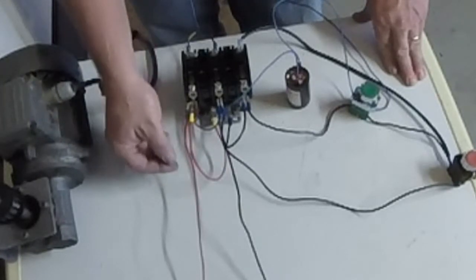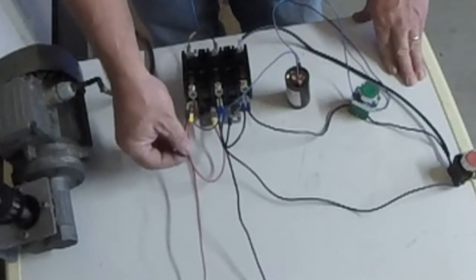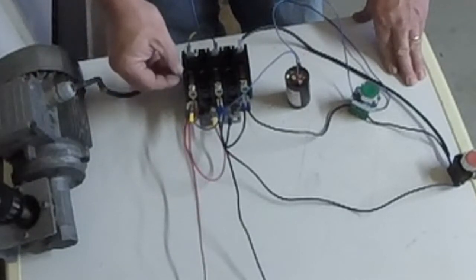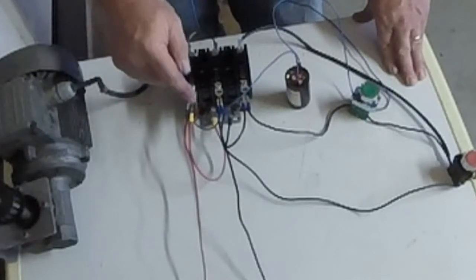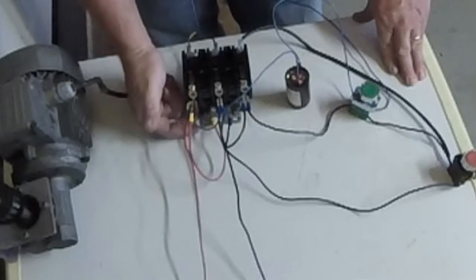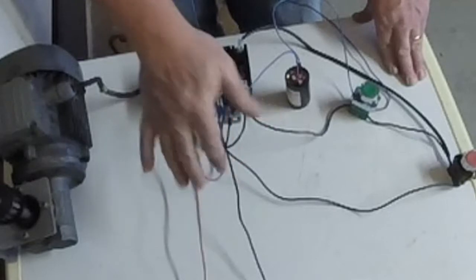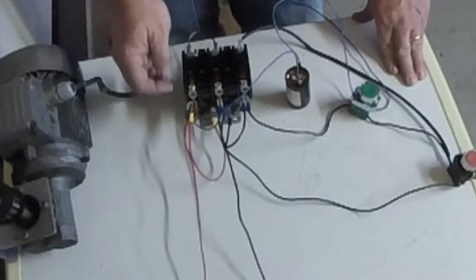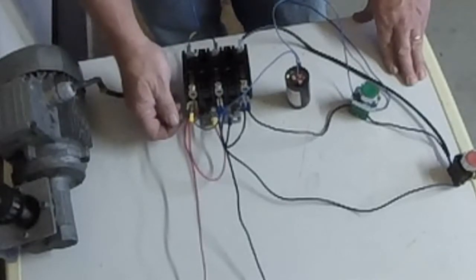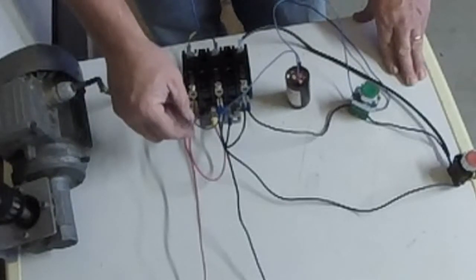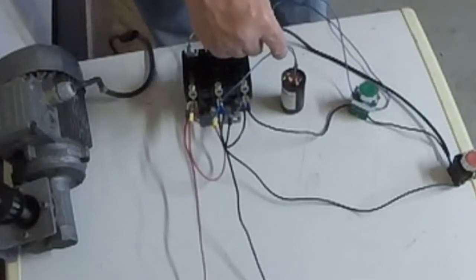Basically what happens here is we have incoming power. This power is split right here at its junction, the first pole of the contactor. It provides power for one side of the coil. This coil is 240 volt operation, so we'll be using both leg lines in order to bring the coil voltage to operate this magnetic starter.